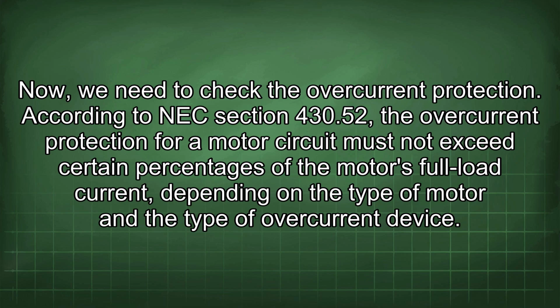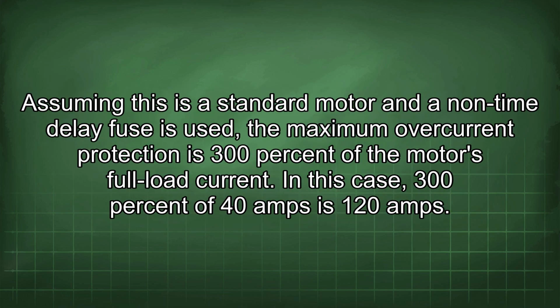According to NEC Section 430.52, the overcurrent protection for a motor circuit must not exceed certain percentages of the motor's full load current, depending on the type of motor and the type of overcurrent device. Assuming this is a standard motor and a non-time delay fuse is used, the maximum overcurrent protection is 300% of the motor's full load current. In this case, 300% of 40 amps is 120 amps.